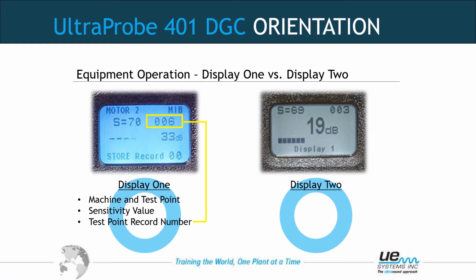006 is the actual test point record number. It correlates to the nomenclature motor 2, motor inboard bearing. You can have up to 400 test points in one route. This is generally too many. 50 to 150 test points is the normal.